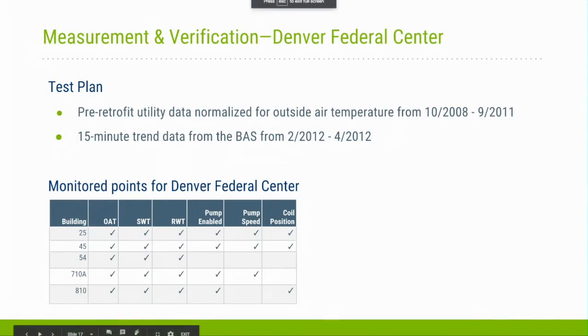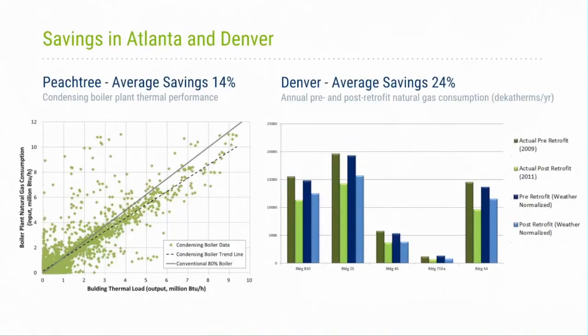Next slide. So this is the takeaway on savings. In Atlanta at the Peachtree, they saw approximately 14% savings, and in Denver, across the 5 buildings, we saw 24% savings. The slide on the left is looking at natural gas consumption relative to the thermal load in the building, and those are lots of data points from the analysis. The condensing boiler had a lower slope, was using less natural gas per thermal load than the conventional 80% boiler, which is the solid gray line.